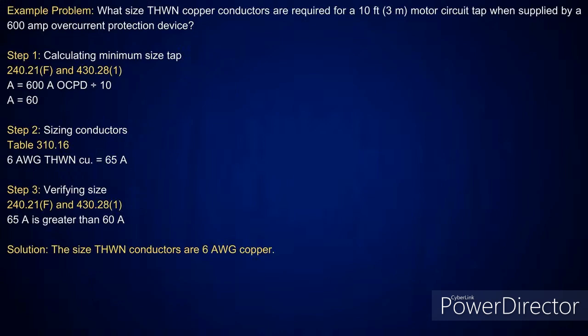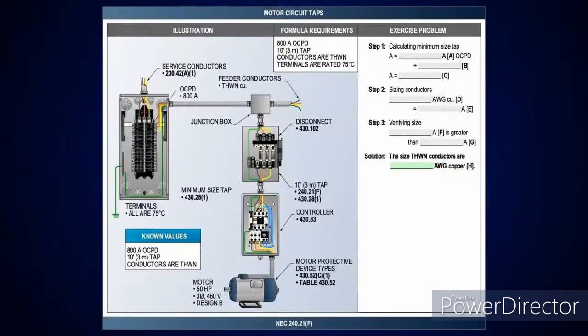You've got 600 amps upstream, divide by 10 gives you 60 amps. I go over and look at Table 310.16, the size of conductors. The next size above that is 65 amps, which is the number 6 conductor. And 65 amps is greater than the 60 amps that's calculated. There's how you do your conductors. That wasn't hard. See there? And here it is. We're showing you where a tap's coming down. I'm showing you the disconnect. I'm showing you the controller and going to the motor. That's a pretty sweet looking illustration. Done.